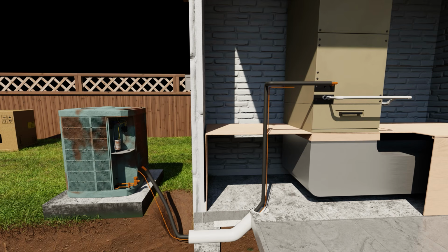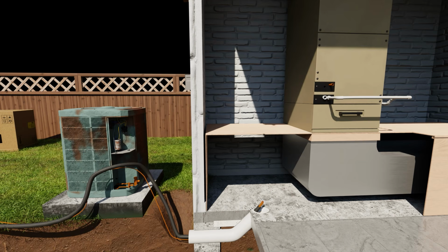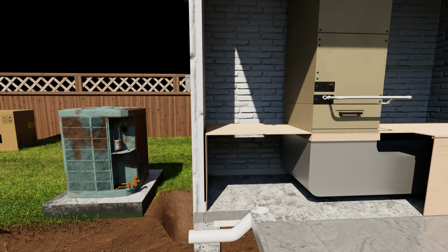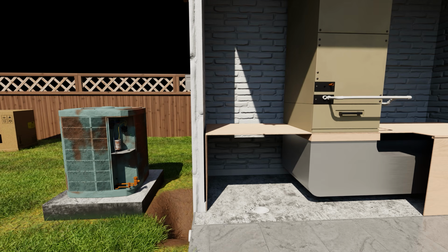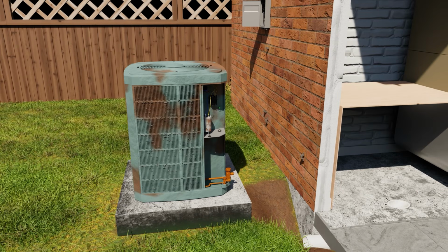Now you can pull out the old copper and drain line if you're replacing both and prepare to run new copper. This is if you're not doing the pipe wiper procedure. This is in cases when you're replacing the copper line set and not reusing it. Next, we're going to show what to do if you're going to replace the concrete pad.